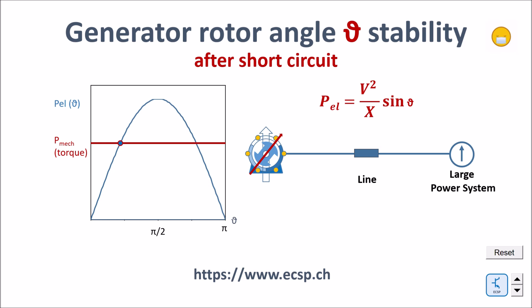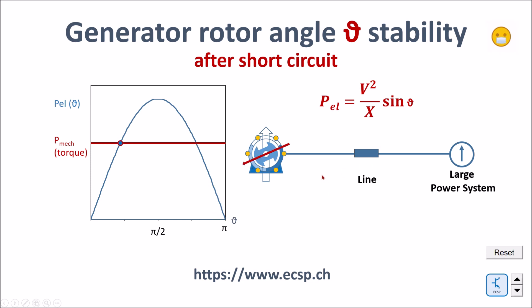Now one of the major challenges: a short circuit on a line. I assume my generator is running and delivering power to the grid. Then I have a short circuit on a line. I disconnect the line for 300 milliseconds. You see how this generator oscillates. The oscillation must not exceed the second equilibrium point of the machine — otherwise we will lose control of the generator. In the second run, I leave the breakers open a little bit longer — maybe 450 milliseconds — and then this point will exceed the second equilibrium, and the generator will accelerate uncontrolled.